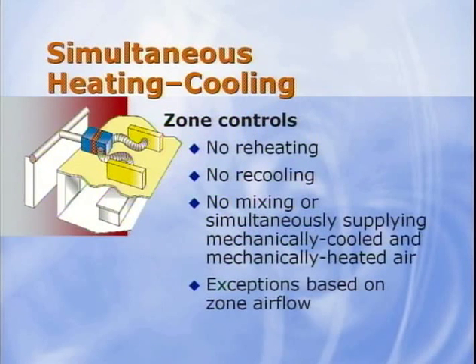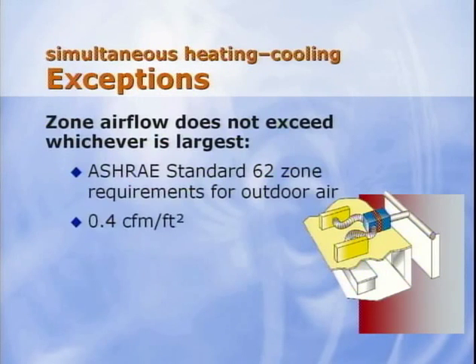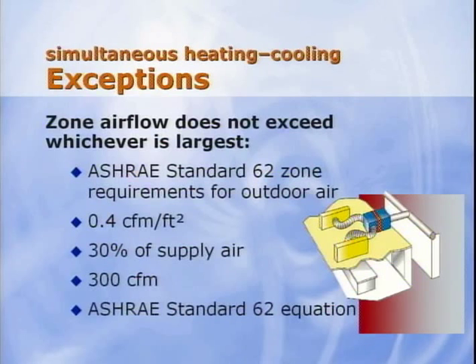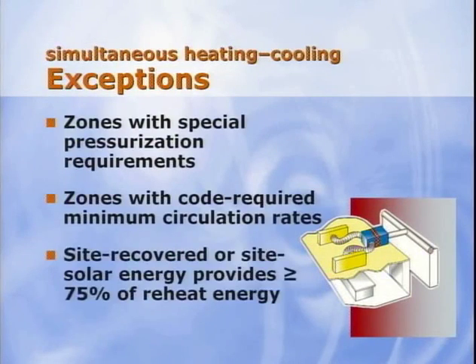Simultaneous heating and cooling is not allowed unless at least one of the following exceptions is met. From a comfort conditioning perspective, before reheating or recooling can be performed using new energy, the supply airflow in the zones must be reduced to the largest of the quantities shown here. Many variable volume systems can be designed and operated to comply with one of these airflow limits. You may do any amount of reheating if at least 75% of the reheat energy is site recovered or site solar.